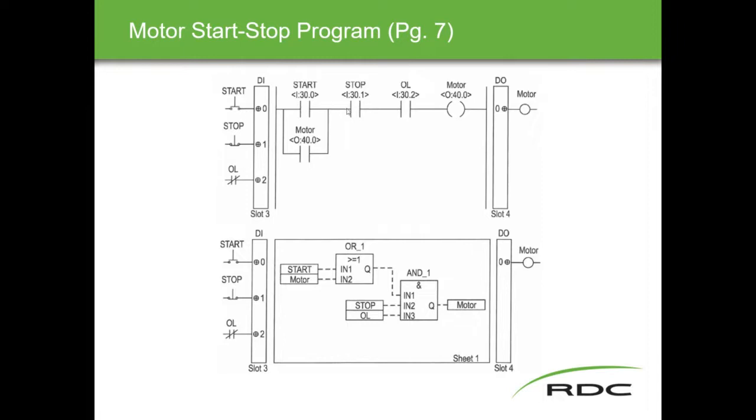So what's it saying? It's saying that if we press start and stop and the overload is good, then the motor will energize. Okay, that's one of the things that we're saying. The other thing we're saying is if the start or the motor and the stop and the overload are good, the coil will be on. So all we're doing is making the translation here.